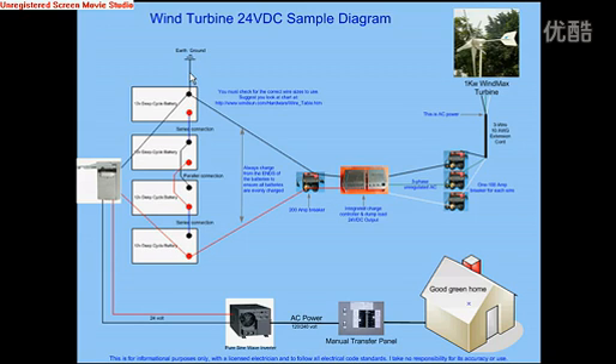All of the connections need to go to an earth ground. So all negative connections that you see in this diagram share a common earth ground. It's not a viable alternative to just connect everything to the negative of the battery without an earth ground. So from the batteries you go, again from the outermost posts, through a DC disconnect. And from the DC disconnect, you have 24 volts going to your pure sine wave inverter. The pure sine wave inverter then converts the 24 volt power to AC power, 120, 240, which can go to either a manual or an automatic transfer switch, and then from there to your house.